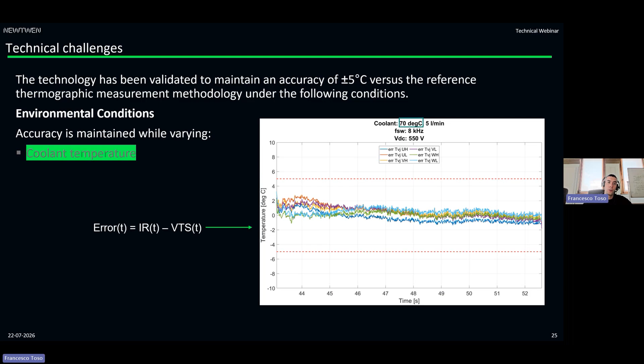As I mentioned before, the third challenge was on the manufacturing tolerances. Let's think about two different phenomena. One is manufacturing tolerance, in the sense that module by module, even if on paper they are identical, in reality they are not, because of all the processes when you are manufacturing it, the impurities, different pressures, etc. So it could be that from the data sheet you have a certain RDS on, the nominal value, but actually there is a variance around that, and this variance can also be 20%. So you can have in some unlucky inverters, power modules with the RDS on 20% higher. And what does it mean? It means that with the same current, you achieve higher temperature with that.